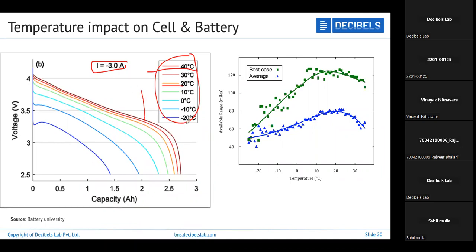If the same cell, if you draw 3 amps at minus 20 degrees Celsius, the capacity you get is only this much. So it means there are some parameters you need to put in your model, that if the battery temperature goes above or below specific limits, the amount of capacity you can expect is only this much. If those temperature variations are too much, you should be able to develop an active cooling system to ensure the battery stays within specific temperature limits.